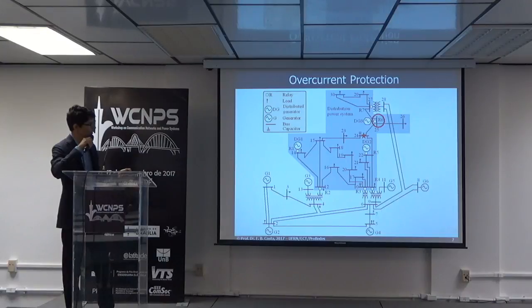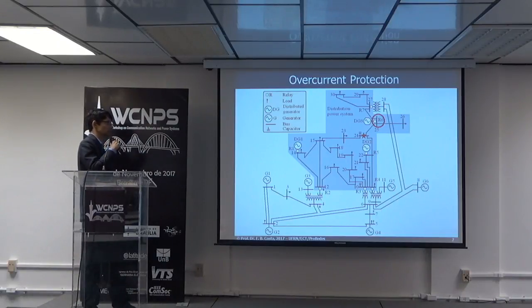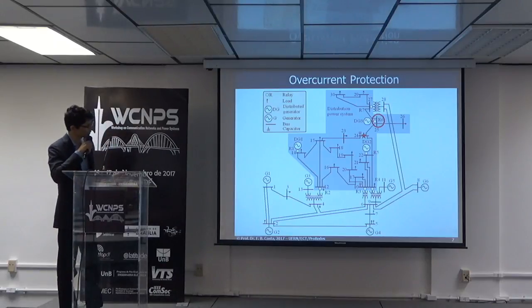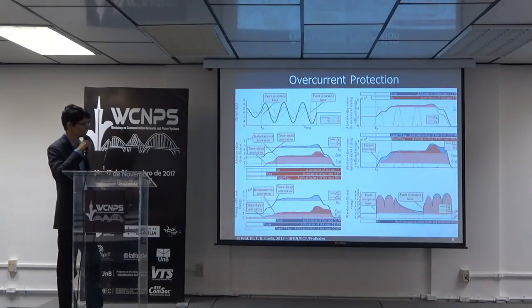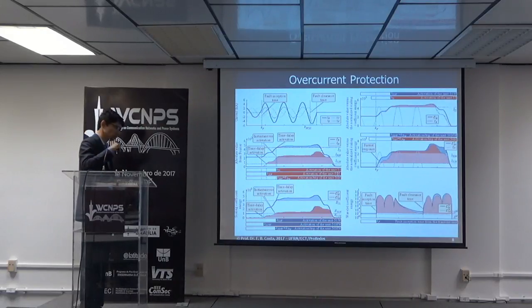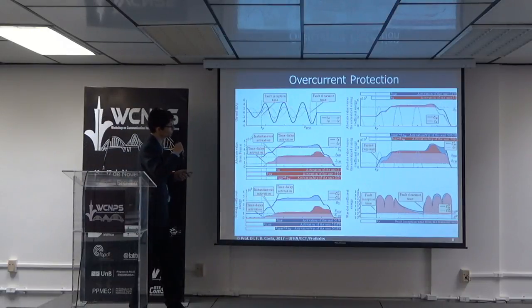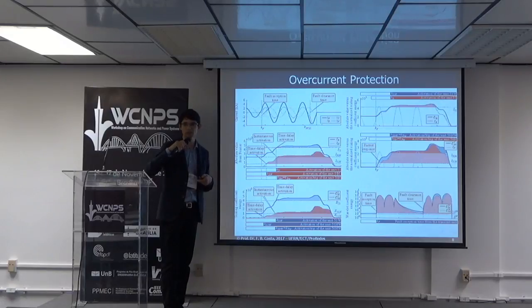For instance, regarding the overcurrent protection, here we have a complex power system composed of a distribution power system with distributed generators, connected to a transmission power system. And we have a relay here and a fault here. In this case, we have a single phase to ground fault at phase A. The performance of the conventional overcurrent protection was compared to the wavelet-based version of the overcurrent protection.